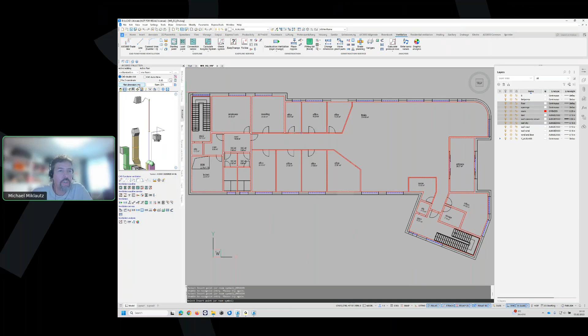So if I prefer to work in ventilation instead of cubic meters per hour, maybe with liters per second, it's only one switch to do this. Now I restart the function, and the software asks for liters per second, and all values are recalculated in real time. Formerly it was 150 cubic meters per hour, now it's 41.67 liters per second.